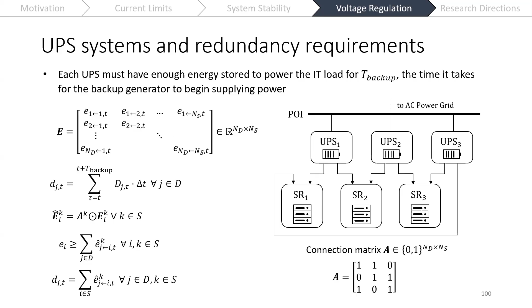So in the case where that swing UPS is out, each UPS just has to be able to satisfy its own load here. Here, E sub I is how much energy we have in UPS I, and D sub J is how much load we have at server rack J. Here, this J should just be an I. So it's saying that the amount of energy that we have in our UPS has to be able to satisfy the server rack it's connected to.